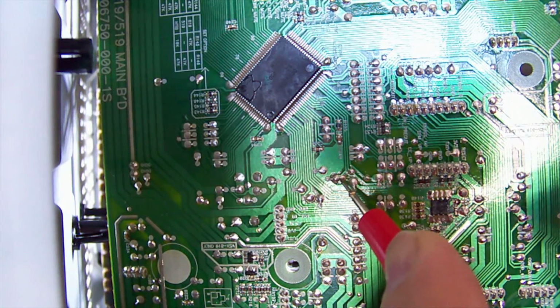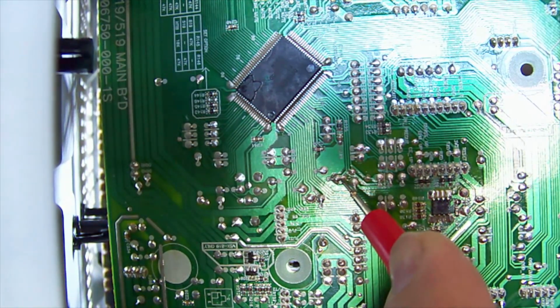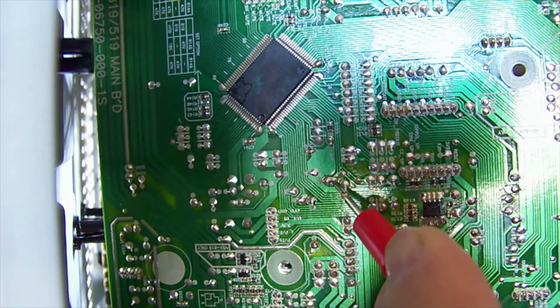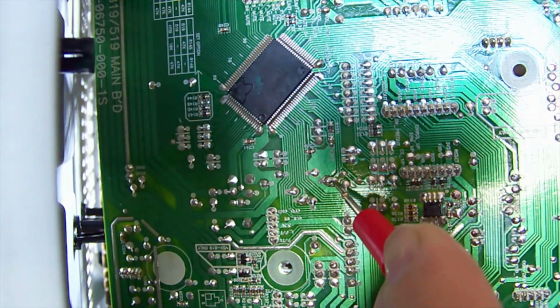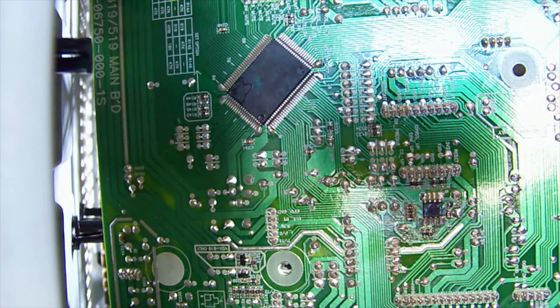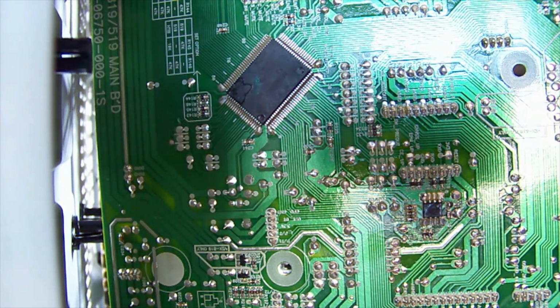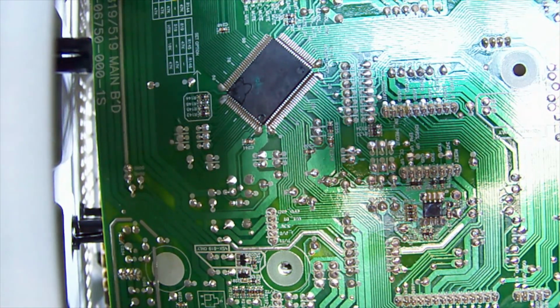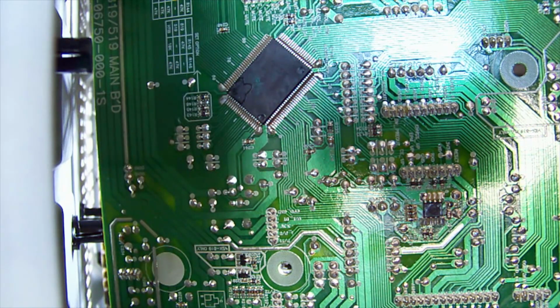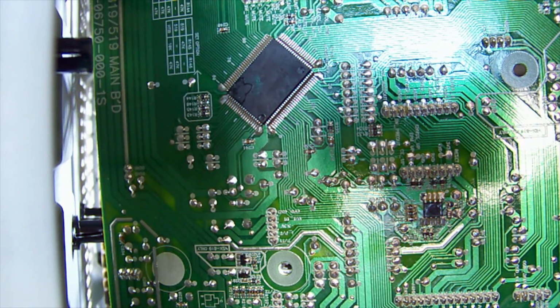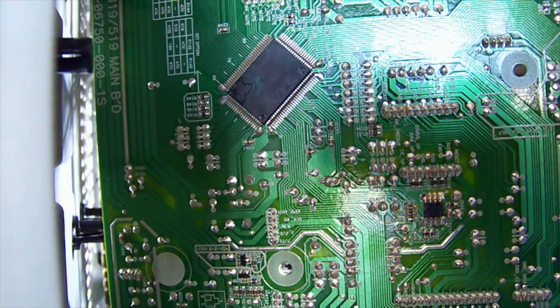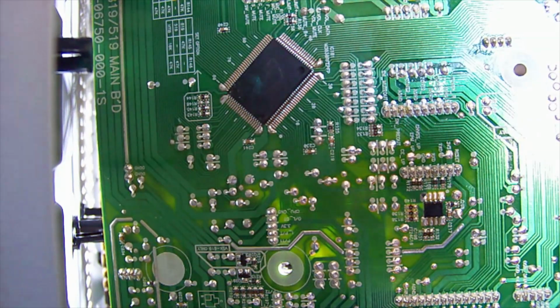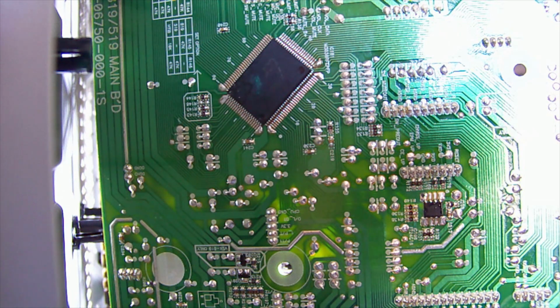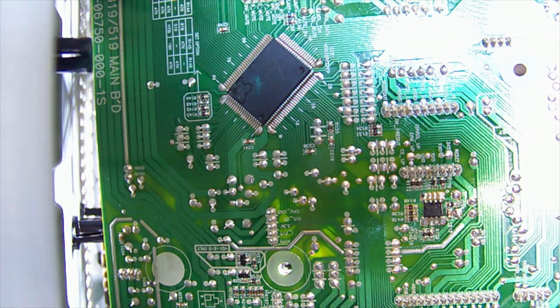Trace through from the front to here, which goes up to the processor, and just to make sure the signal is getting into the processor, when I push the power button I see it drop to 0, so I know the processor is being told to turn on, and there is no reason why we should not be getting a signal out of the processor to control the relay. So I'm thinking the processor is dead, and I think this is an integrated unit. This is a microcontroller, which means there's no EEPROM, which means I can't just replace it. It's what they call a mask ROM, or it's one-time programmable. I don't know. It's hard coded. Yeah. So the only way to fix this would be to get one off another board.